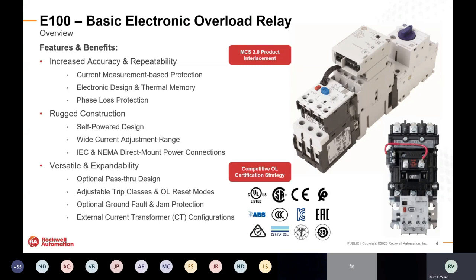You'll see a couple of different images here on the right where the E100 is also offered, very similar to the E1 Plus, in direct mount offerings with Bulletin 100C and Bulletin 500 contactors, meaning you have power stabs that connect directly to those contactors, so you don't need any extra wiring, which simplifies installation and commissioning.